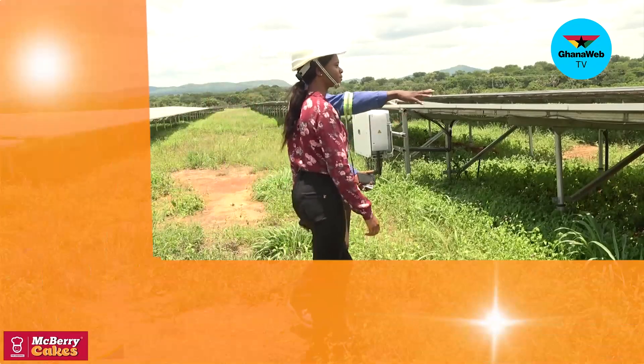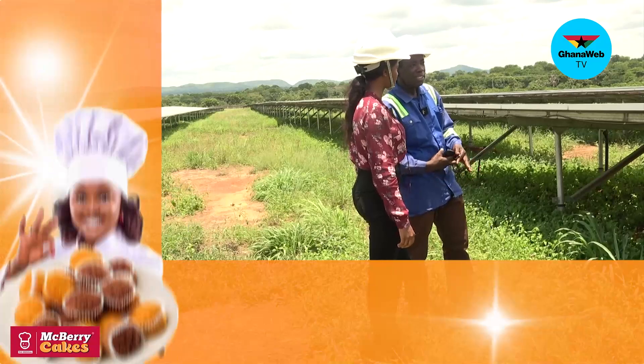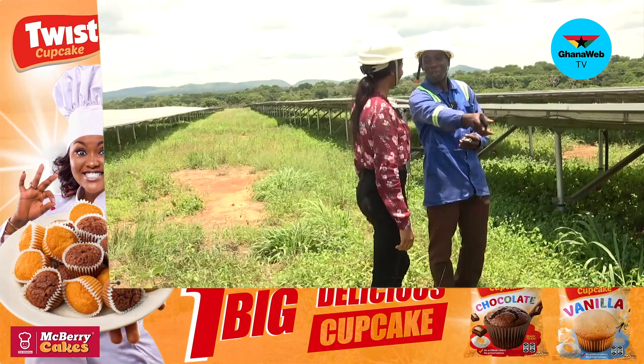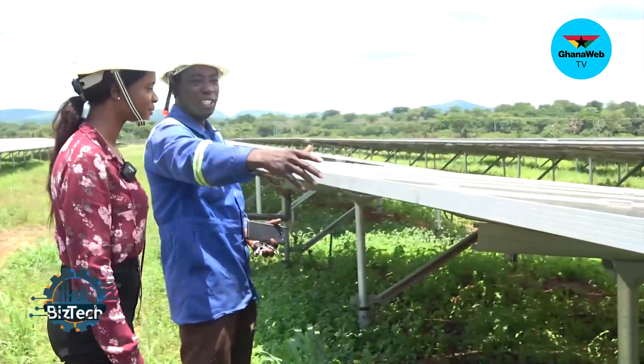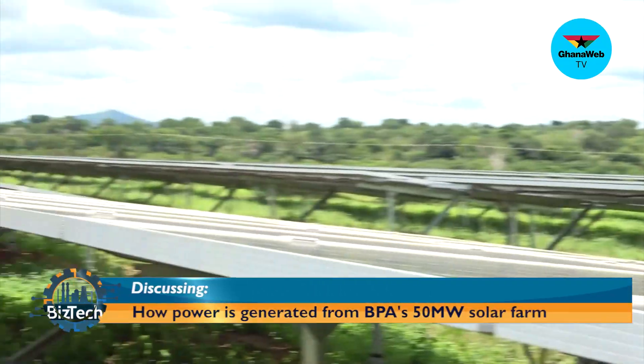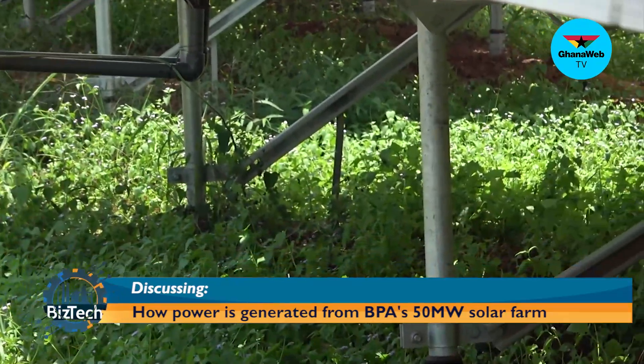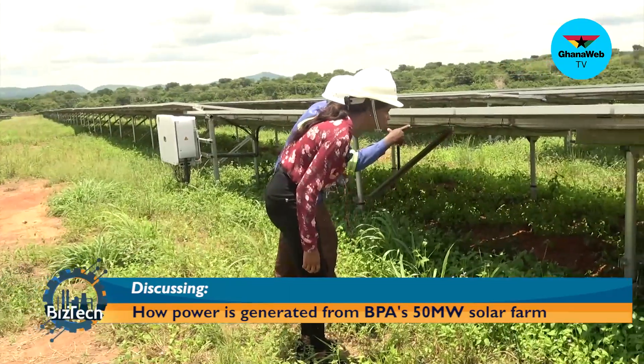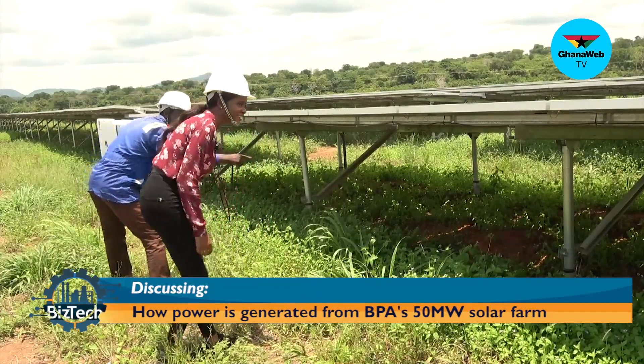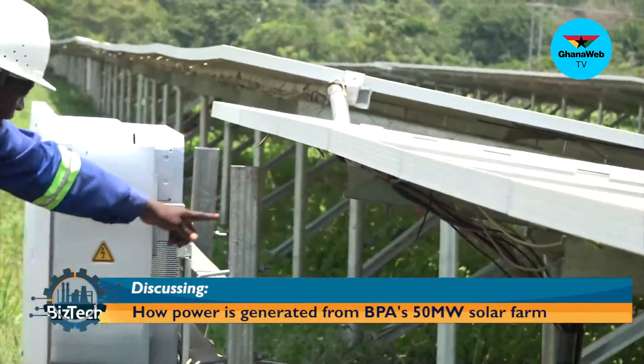These are the solar panels. They are connected on power strata, known as sub-arrays. Each sub-array contains 60 panels — 30 up and 30 down. That is the whole structural unit. From here we have what we call strings. The cables are known as strings, and we identify them by strings. This one is four strings: two from this end and two from the other end — the first 30 and another 30. It's connected and comes to the inverter.